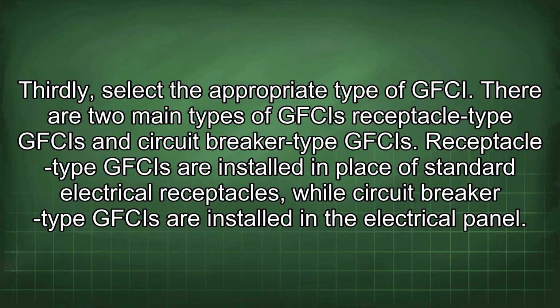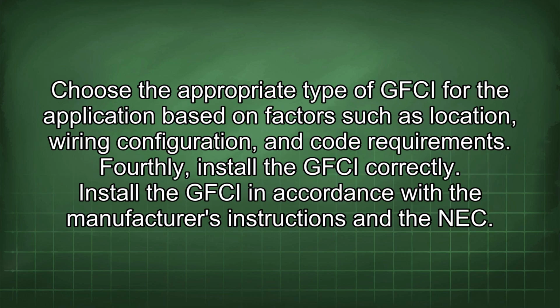Thirdly, select the appropriate type of GFCI. There are two main types of GFCIs: receptacle type GFCIs and circuit breaker type GFCIs. Receptacle type GFCIs are installed in place of standard electrical receptacles, while circuit breaker type GFCIs are installed in the electrical panel. Choose the appropriate type of GFCI for the application based on factors such as location, wiring configuration, and code requirements. Fourthly, install the GFCI correctly. Install the GFCI in accordance with the manufacturer's instructions and the NEC.